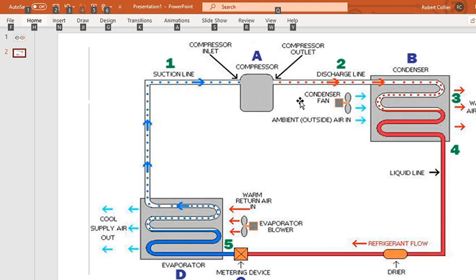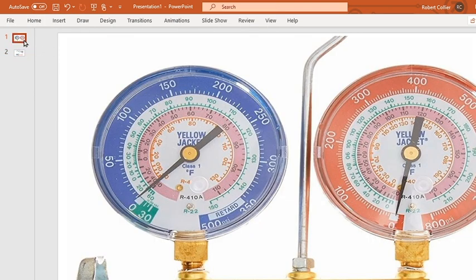At this point, leaving the compressor, for example, let's say it's 150 psi. That would put us at 150 psi on the 410A, which is the purple line, would put us at about 85 degrees. But let's use that number. That's not exactly right for all circumstances, but for this demonstration it will be.